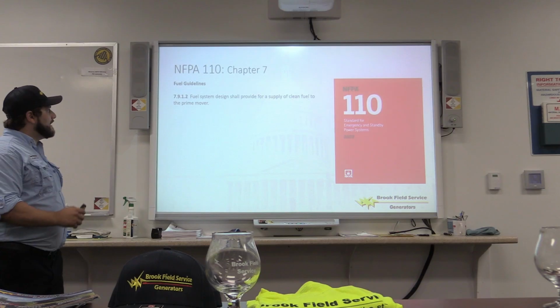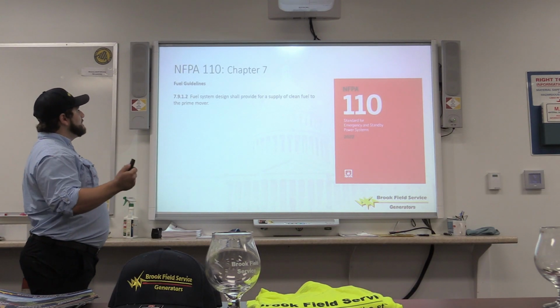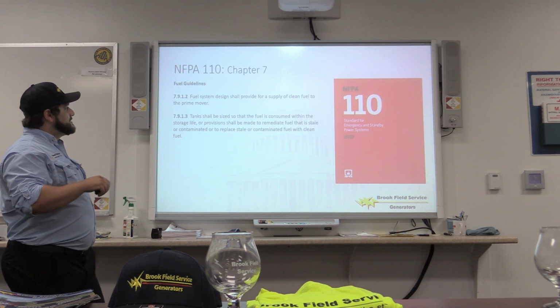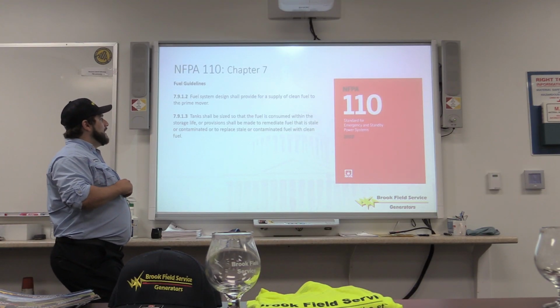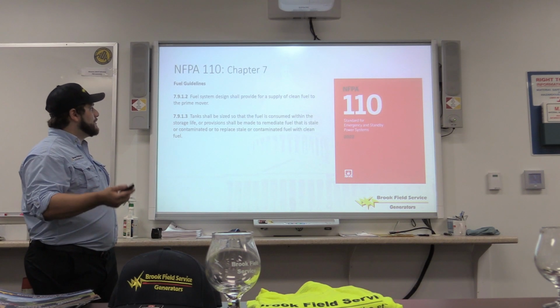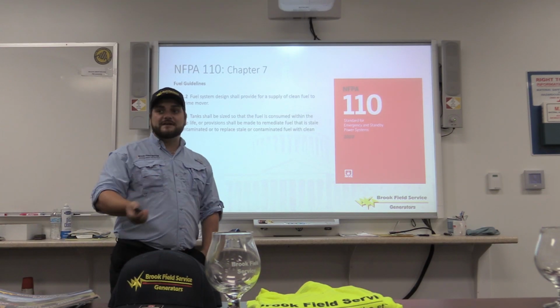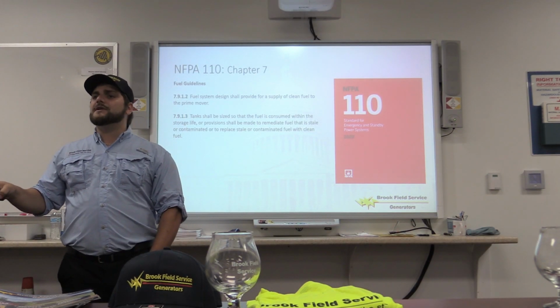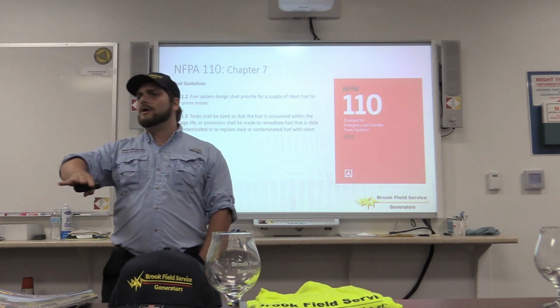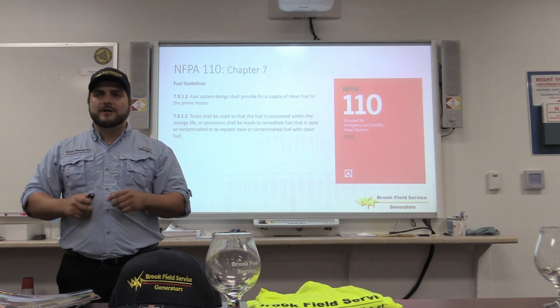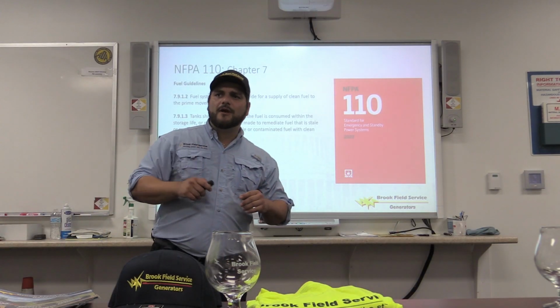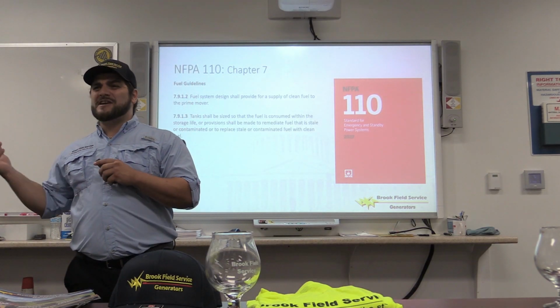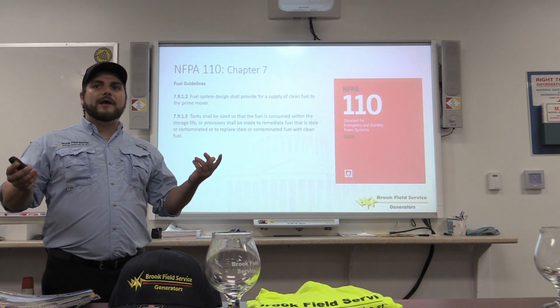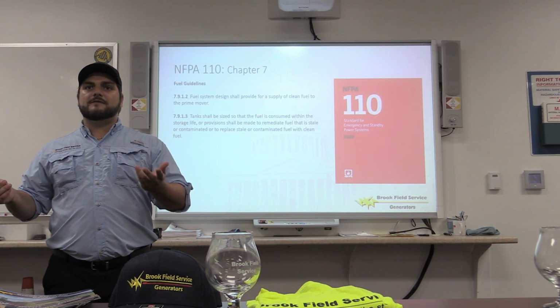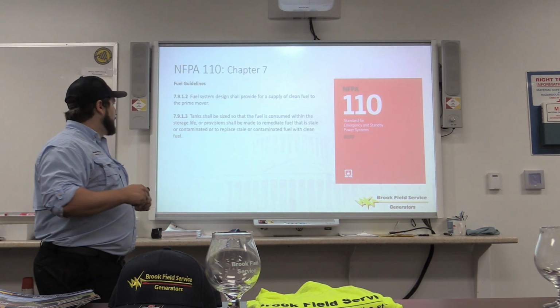Fuel guidelines. Fuel systems design shall provide a supply of clean fuel to the prime mover, and tanks shall be sized so that the fuel is consumed within the storage life. Provisions shall be made to remediate fuel that is stale or contaminated, or to replace stale or contaminated fuel with clean fuel. Again, I left a lot of detailed stuff in here because I know some of you are wastewater operators or folks that aren't part of water operation. Regardless, it's important when you think about diesel degradation. There's a certain lifespan, and if you're not within it, you risk clogging your system and, obviously, system failure.